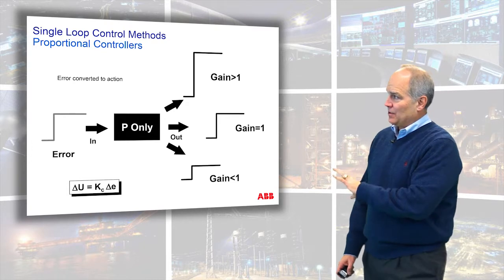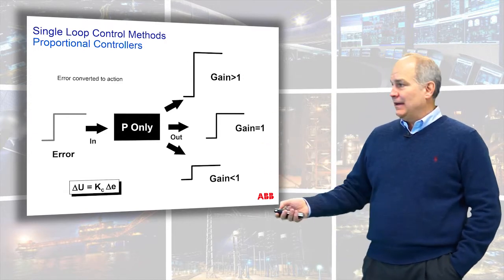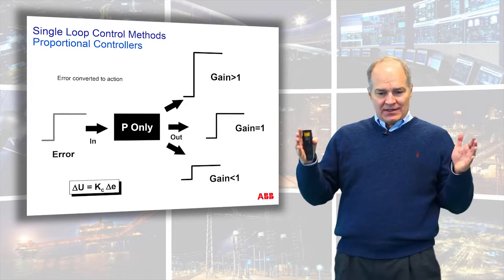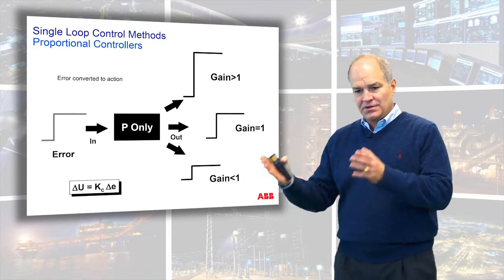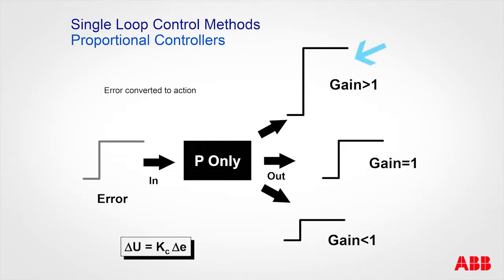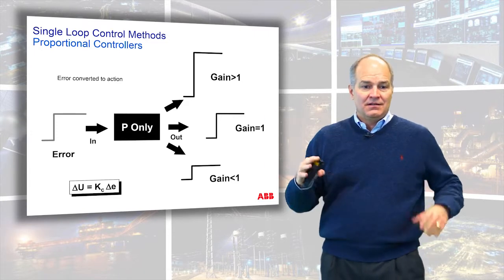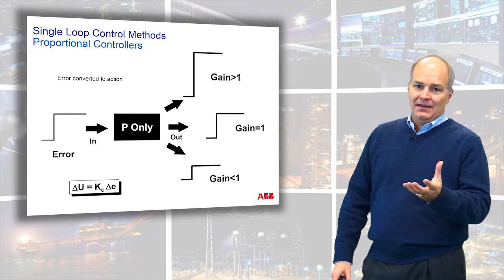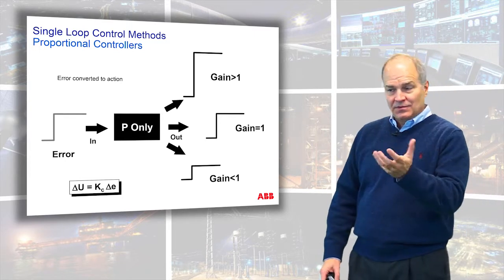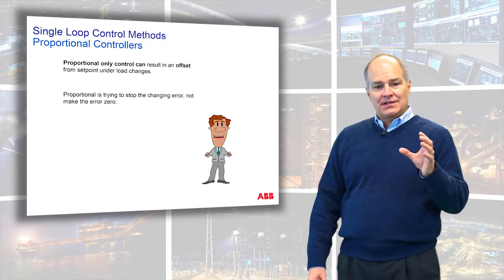To summarize proportional: the output is proportional to the shape of the error. For a step-change error, if gain is greater than one the output is bigger; if gain equals one they're matched; if gain is less than one the output is less. The gain adjusts the proportion, and you need to bias the gain with the process gain — we'll cover that in tuning rules. However, proportional-only control results in what's called an offset.